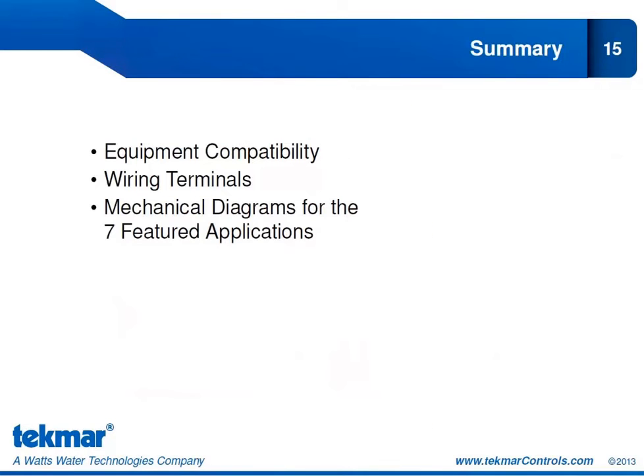So in summary for this training segment, we looked at the equipment compatibility for the 654. So it is a snowmelt control that can operate an on-off or modulating boiler, and we can also operate an electrical contactor for electric applications. We took a look at the wiring terminal, so we have a good idea of what we can connect to the 654. And we also looked at how that would affect connecting to a system pump or providing an enable to a boiler, how we would need to use those isolation relays. And lastly, we looked at the mechanical diagrams for the 7 featured applications so that you all have a very solid understanding of the types of applications the 654 has been designed to control.